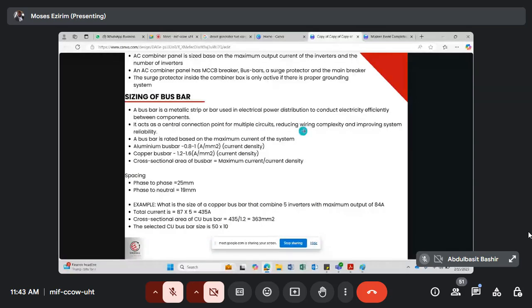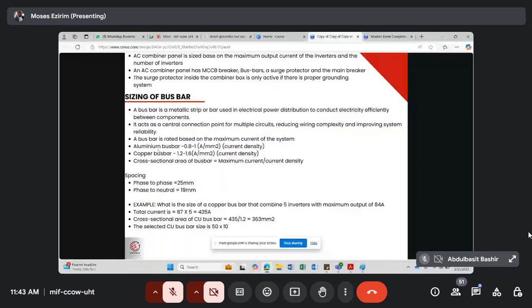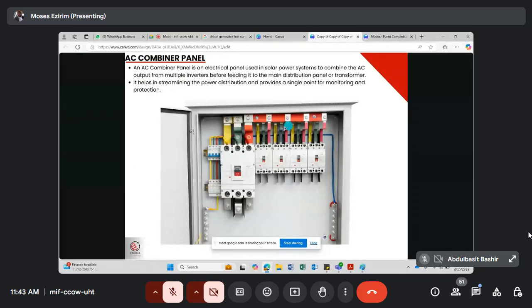Reducing wiring complexity and improving system reliability. Now we have an aluminum bus bar. The current density is between 0.8 to 1. The area of a bus bar is sized by the maximum current divided by the current density. Now, if I'm sizing a bus bar, I can say this bus bar is 200 amps. I can say this bus bar is 500 amps. How do you know it is 500 amps?